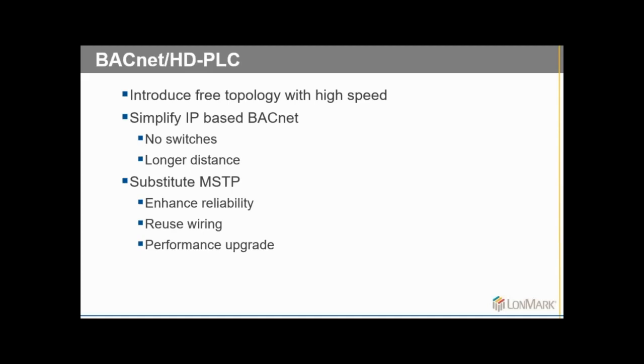So you have seen in some slides before, it is only a piece of software we put on the HD-PLC chip. Simplify that, it is BACnet IP, which is running on HD-PLC without having switches and on the longer distance. It can substitute MSTP. MSTP is a nightmare regarding reliability, regarding collisions, token loss, and so on the RS-485 network. And you can even reuse the existing wiring, MSTP wiring, to run HD-PLC on that. So it can boost your performance in the BACnet network.